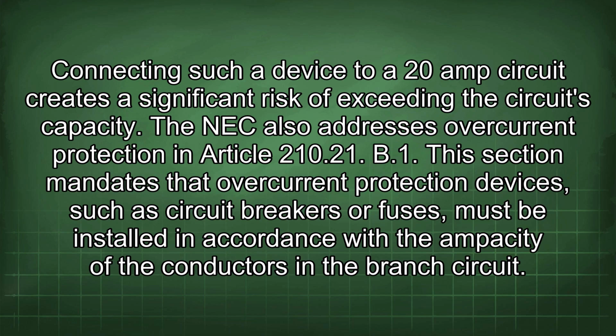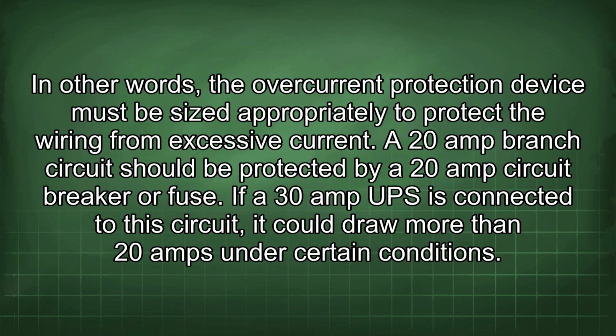The NEC also addresses overcurrent protection in Article 210.21(B)(1). This section mandates that overcurrent protection devices, such as circuit breakers or fuses, must be installed in accordance with the ampacity of the conductors in the branch circuit. In other words, the overcurrent protection device must be sized appropriately to protect the wiring from excessive current. A 20 amp branch circuit should be protected by a 20 amp circuit breaker or fuse.